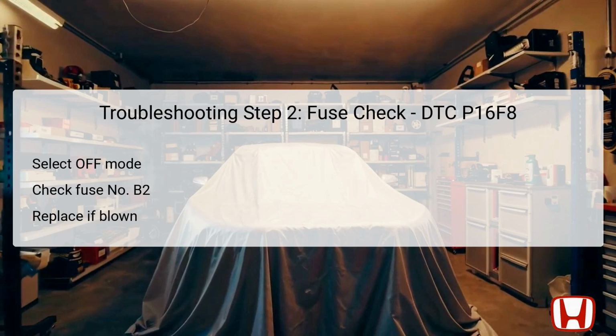If the fuse is found to be okay, you should continue to the next troubleshooting step. However, if the fuse is blown, it needs to be replaced immediately. Additionally, it is vital to check for any short to ground in the circuit associated with this fuse, as persistent fuse failures can indicate deeper electrical issues within the system.